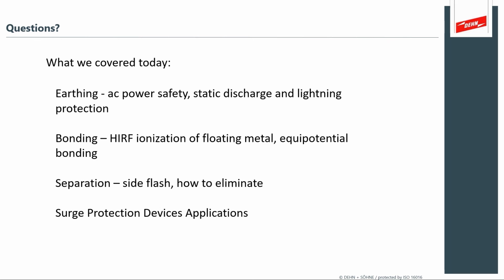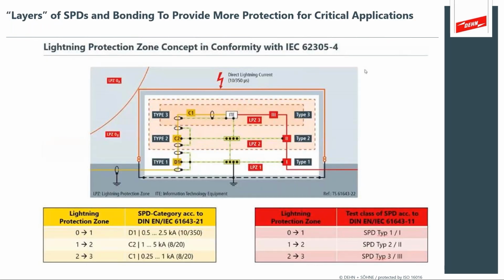Well, allow me, I don't like to do this, but I'll back up one slide. So the IEC Type 1 device is considered to be rated for the lightning current that you would get induced from a ground potential rise. A lot of times people are concerned that the lightning current is coming in on the AC power, which of course can happen. But on the AC power, you've got things like transformers and your meter base that can also provide some degree of actual isolation. But when the lightning currents come in through the down conductor and get injected into the earth system, you have ground potential rise. And that in the IEC methods is considered to be a Type 1 device. And they're tested to direct lightning current withstand for a 10 by 350 pulse.